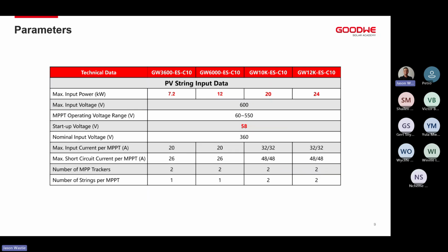Next, and quite unique to GoodWe, is the maximum input power on our PV string input data, as well as the startup voltages and operating voltages of our MPPT. I'll go into a little bit more detail. I'll show you another slide shortly on the input power of our inverters from the PV side. But if we're looking at the startup voltage, all of our inverters in the ES Uniq range start up at 58 volts, and all of them have an operating voltage from 60 volts to 550.